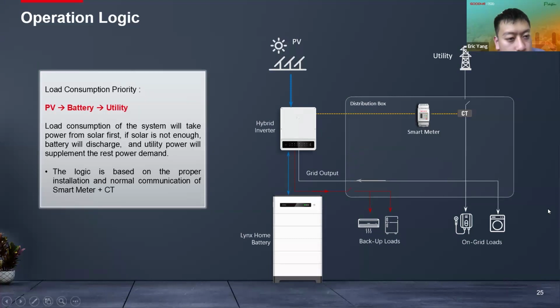And this is the load consumption priority. If the customer has some loads, the first priority is from the PV, and secondly it is from the battery. And if there is no PV and the battery is empty, it will get the power from the utility when the grid is available. When the grid has failed, it will only get the power from PV and battery.